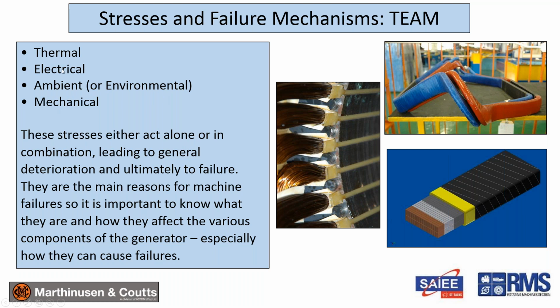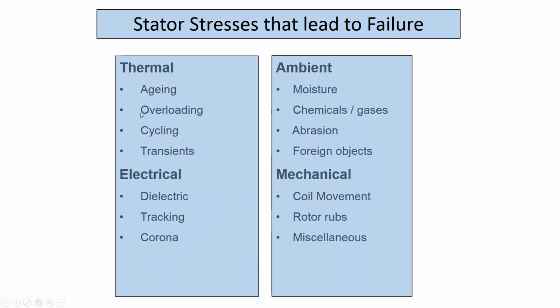And then just as important is the electrical stress, and you'll see that towards the end. All the stresses act together, so the point is one has to consider all the stresses in an electrical machine in terms of determining the thickness of the insulation and other parameters. Again, I won't go into detail here. This goes in a bit closer to your stresses. So you can see under thermal, there's thermal cycling, and then mechanical, there's coil movement.